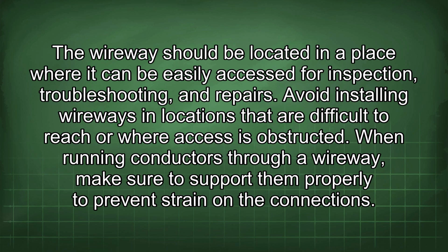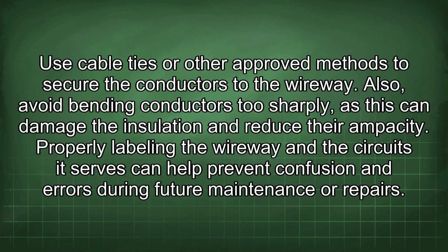When running conductors through a wireway, make sure to support them properly to prevent strain on the connections. Use cable ties or other approved methods to secure the conductors to the wireway. Also, avoid bending conductors too sharply, as this can damage the insulation and reduce their ampacity.